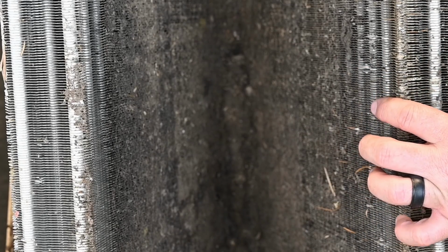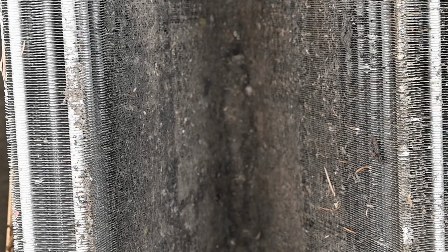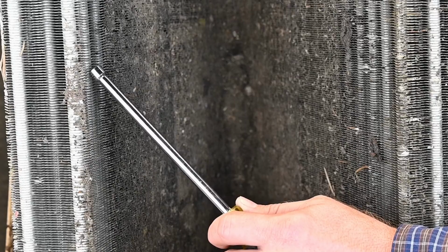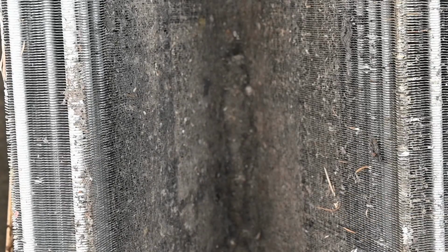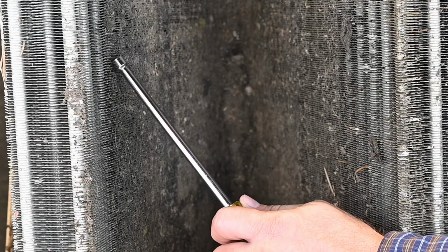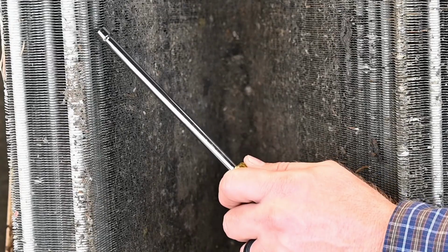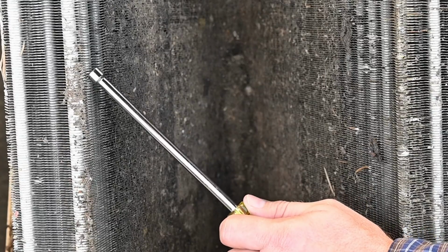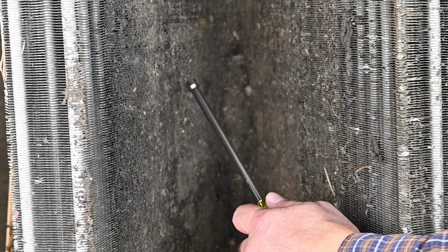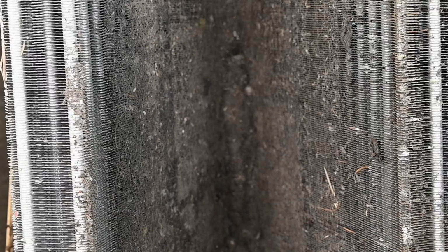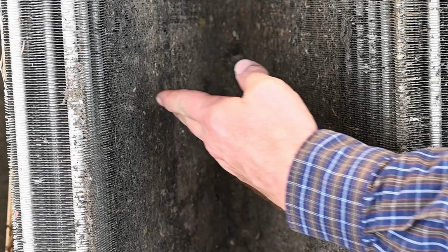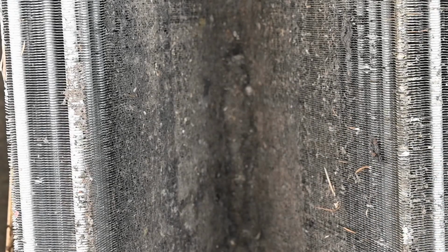Now, they're sharp for a reason. Remember, this coil is turned the other way, but we also dehumidify, so that moisture runs down the very sharp edge and into our condensate removal pan. When that water runs through the sharp edge, everything's doing good. But once we damage, even ever so slightly, or have corrosion on these evaporator fins, that moisture runs down, hits that bad spot, and starts dripping down past. So a lot of times you'll end up with a good drain line, but the evaporator is still leaking water, and the water is literally dripping off of the evaporator coil.